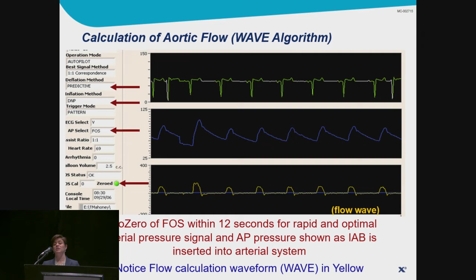Fiber optic catheters, the big question is, why do we need them? Why do we use them? Well, the most important reason is that the fiber optic catheter from Arrow is going to reproduce the arterial pressure waveform in virtually real time. This resulted in an average increase of an hour to an hour and a half more balloon pump support over a 24-hour time period. This simply occurs due to the loss of the delay of the fluid pressure monitoring system.